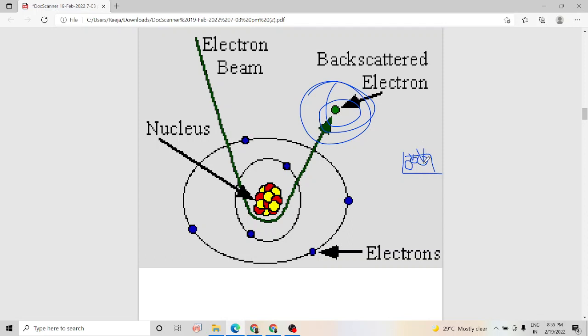For a higher atomic number element, the rate of production of backscattered electrons is high, and we get a bright region in our image. For lighter atomic number elements, the brightness reduces and we get a darker region. So backscattered electron emission is used to detect areas with different chemical composition in a sample, helping us identify different regions having different chemical compositions.